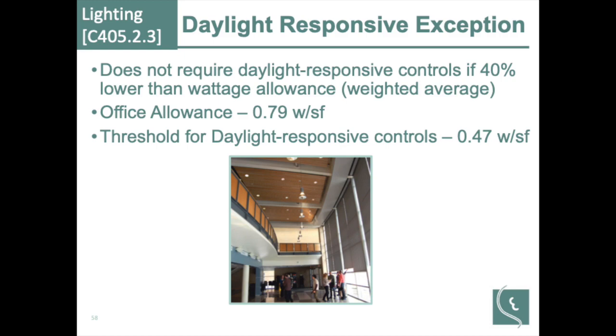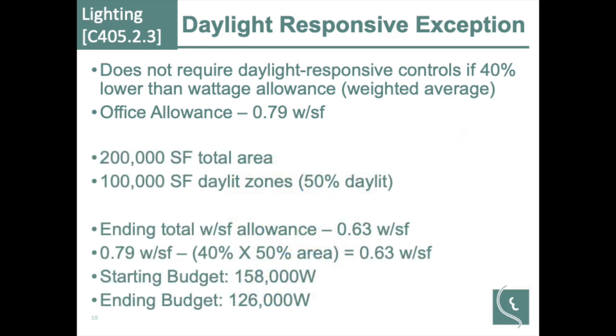Primarily because with LED lighting and things like that, if you install lower wattage, lower power density on the perimeter of the building, the savings for putting in daylight harvesting controls there is about 40%. So if you can reduce the perimeter by 40%, then you don't need that lighting control there to get your 40% savings. So that's why that's in there. The rest is just an example of a breakout calculation of that. It's an example of why that 40% is selected for an exemption for perimeter lighting, daylight.